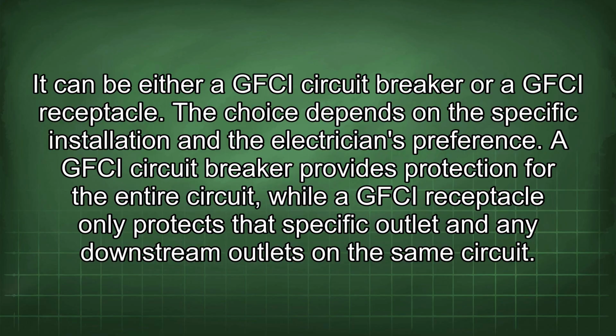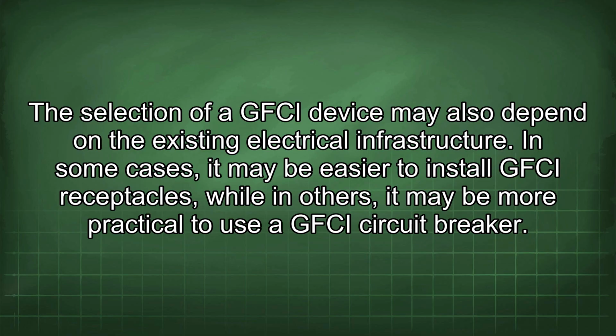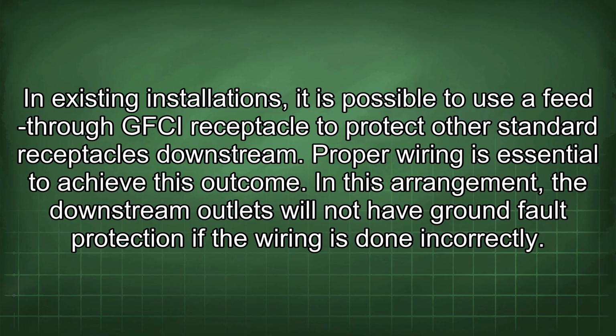A GFCI circuit breaker provides protection for the entire circuit, while a GFCI receptacle only protects that specific outlet and any downstream outlets on the same circuit. The selection of a GFCI device may also depend on the existing electrical infrastructure. In some cases, it may be easier to install GFCI receptacles, while in others, it may be more practical to use a GFCI circuit breaker. In existing installations, it is possible to use a feed-through GFCI receptacle to protect other standard receptacles downstream. Proper wiring is essential to achieve this outcome. In this arrangement, the downstream outlets will not have ground fault protection if the wiring is done incorrectly.